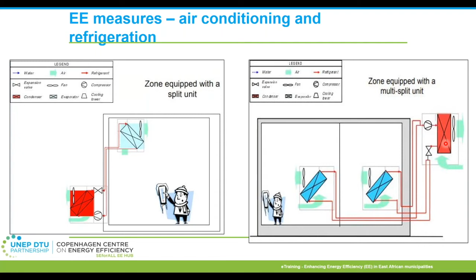So what would be recommended is to have zones for your air conditioning equipment, wherein depending on a specific zone, if that particular zone detects that there are no people there, or the temperature set points have already been attained, then systems like VRV systems, or variable refrigerant volume systems, can actually regulate the extent of refrigerant that is flowing into that particular zone. So that way you have less work done by the compressor, and less energy consumed.